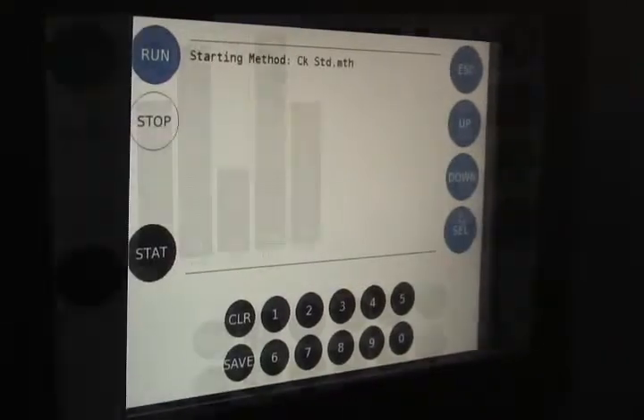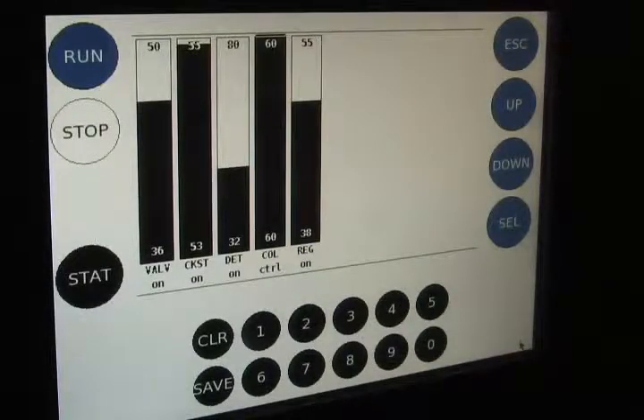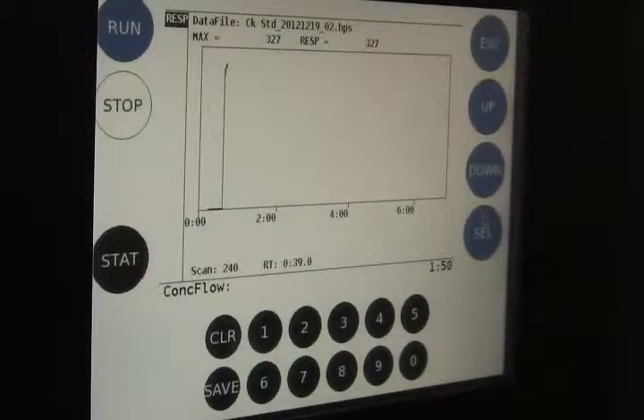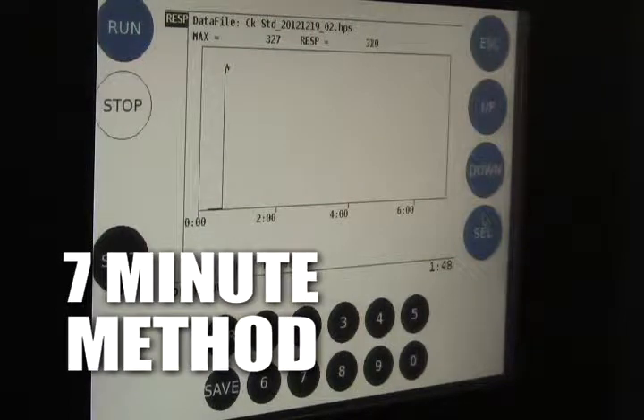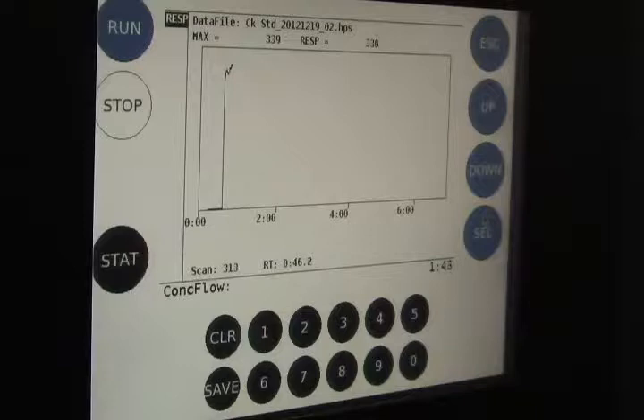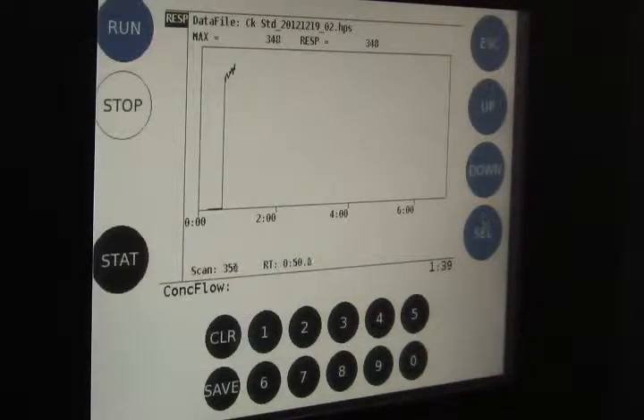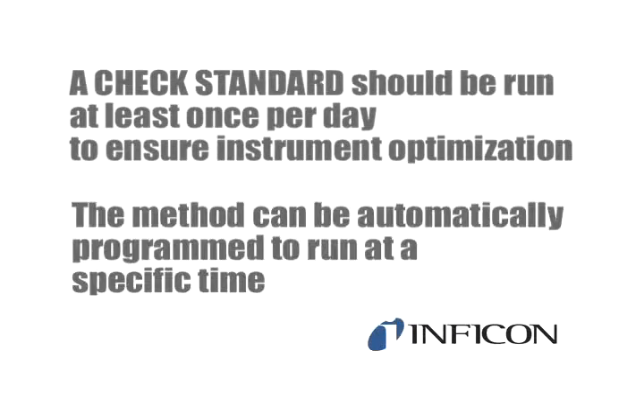Select Check Standard. Upon initializing the check standard method, the CMS5000 will heat the internal components. The zones may be displayed on the front panel. Once the temperatures are stabilized, the 7-minute method will begin. The method can also be initiated from the laptop. The check standard chromatogram is visible on the front panel. Inficon recommends that a check standard is run at least once per day to ensure instrument optimization. The method can be automatically programmed to run at a specific time.